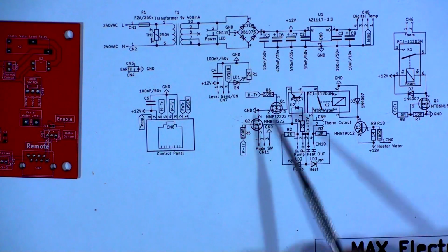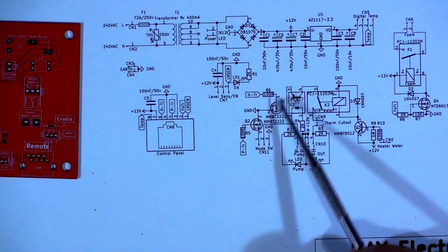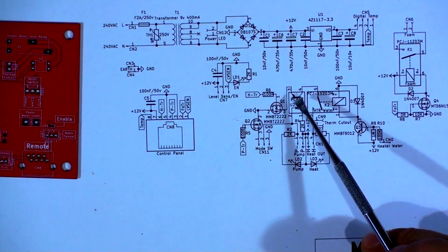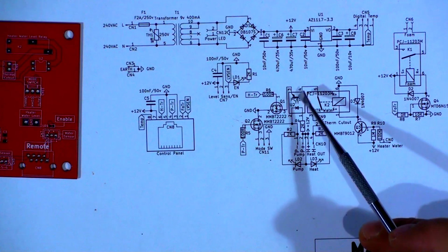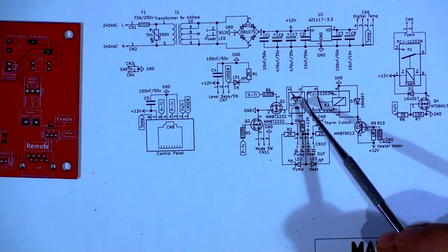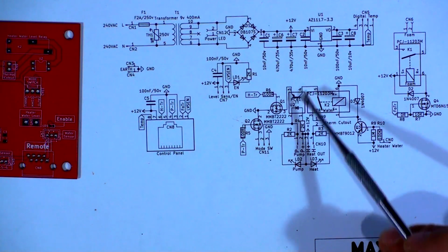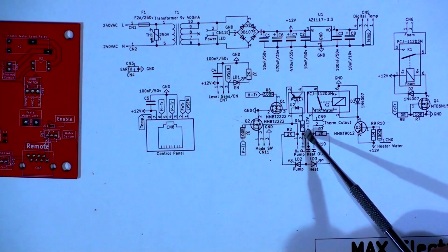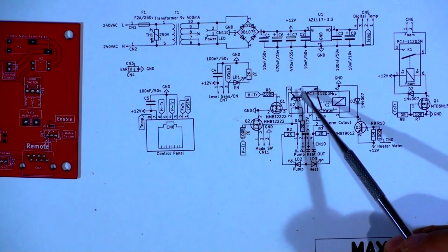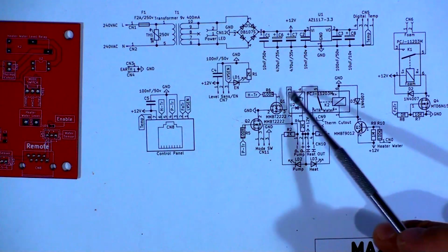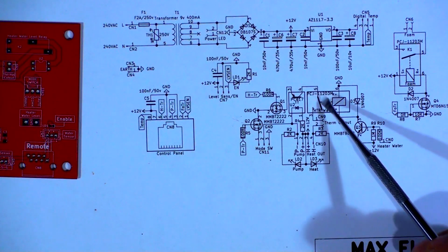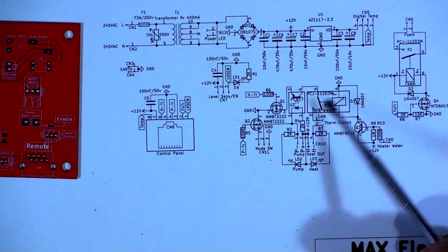So from here, once it's triggered by the panel, by the controller, it goes through that optocoupler. The optocoupler will trigger when the pump is on. So if the pump is on, the signal will not go further. Anyway, let's say the pump is on, it goes through the optocoupler, and then it goes through the relay.